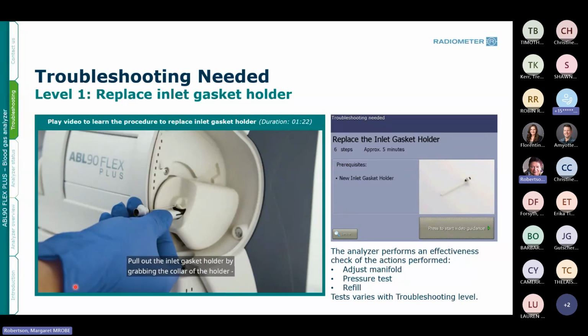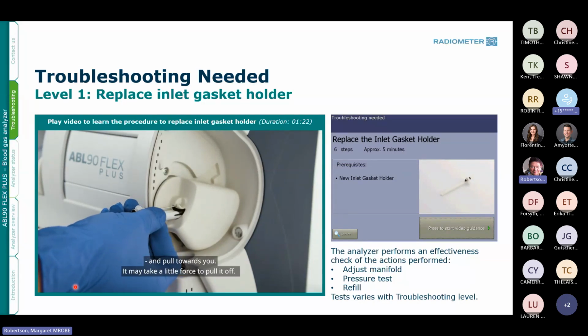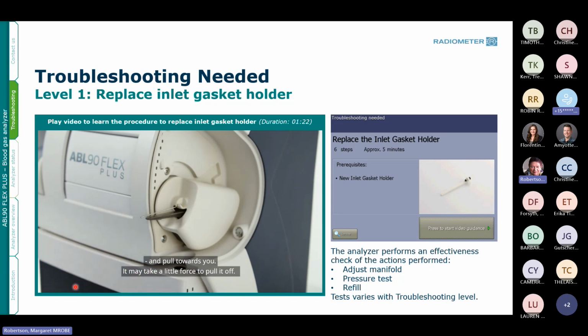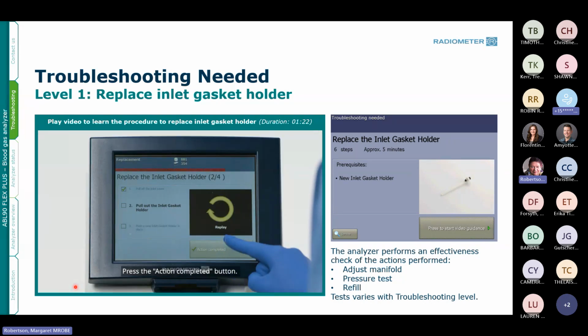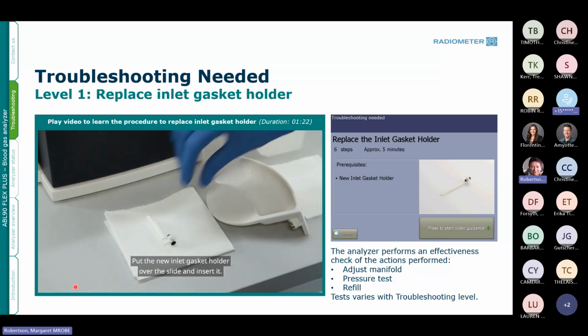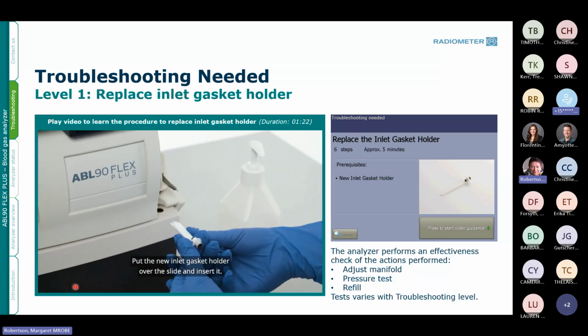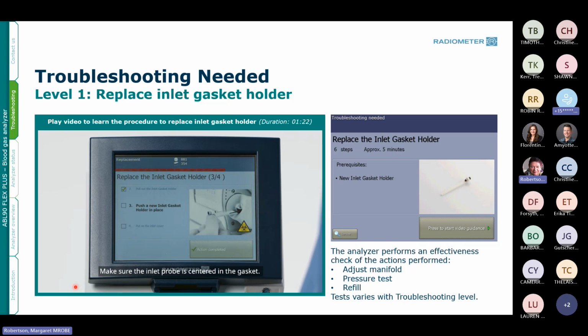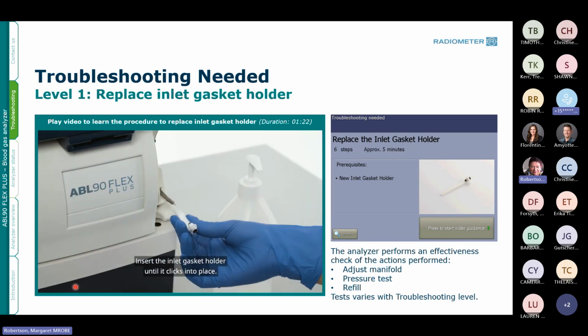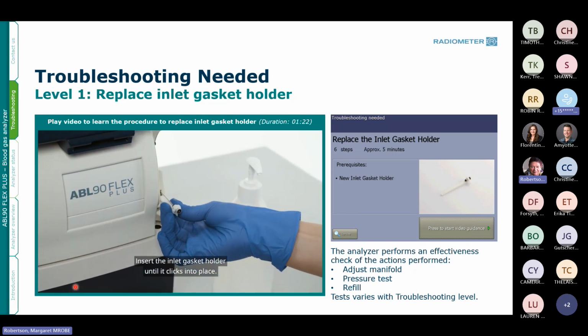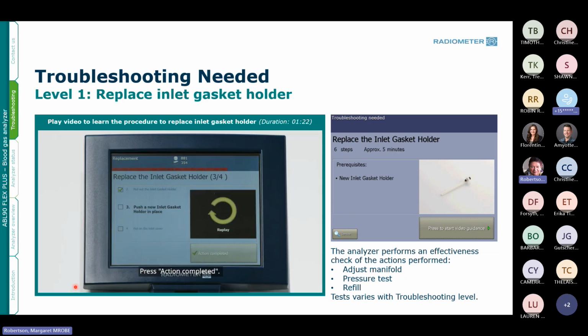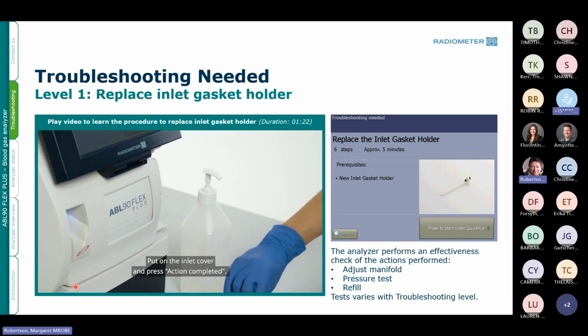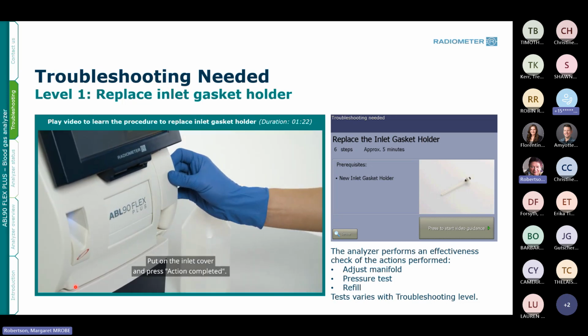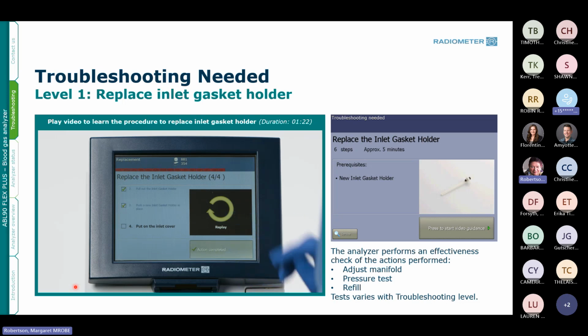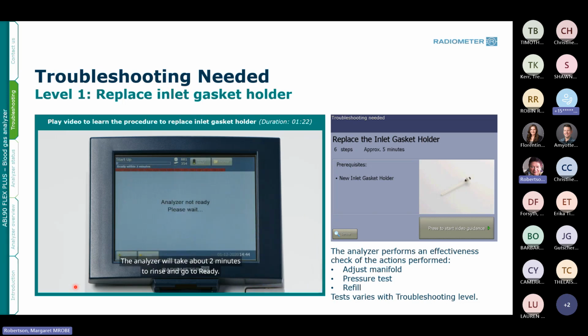Pull out the inlet gasket holder by grabbing the collar of the holder and pull towards you. It may take a little force to pull it off. Press the Action Completed button. Put the new inlet gasket holder over the slide and insert it. Make sure the inlet probe is centered in the gasket. Insert the inlet gasket holder until it clicks into place. Press Action Completed. The analyzer will close the inlet. Put on the inlet cover and press Action Completed. The analyzer will take about 2 minutes to rinse and go to Ready.